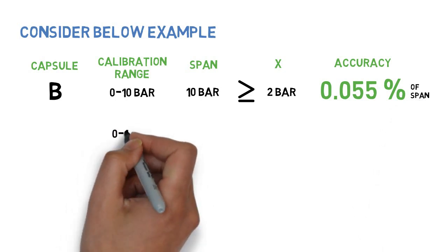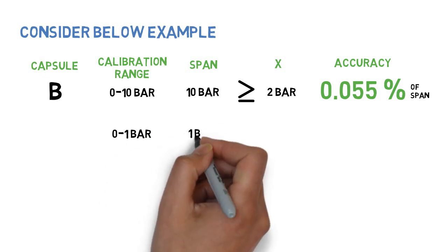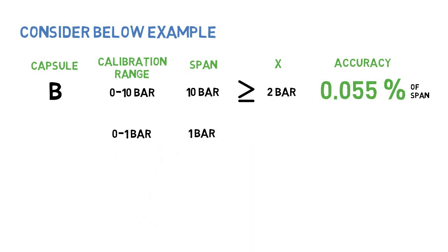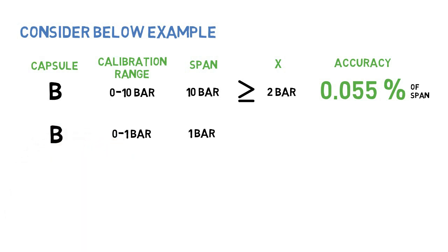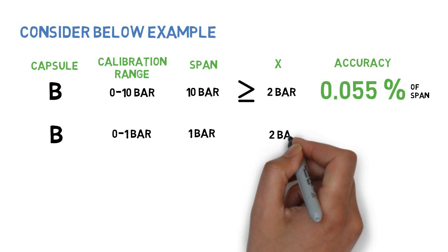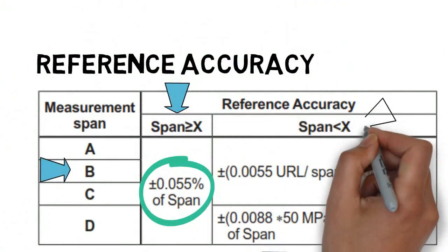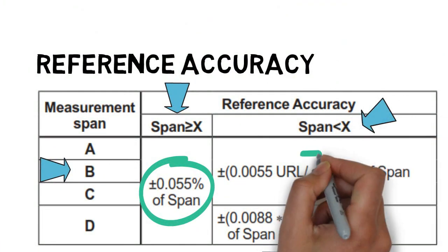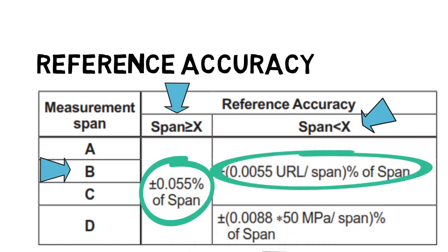Consider another range of 0 to 1 bar. Span is 1 bar. Maintain capsule same as B. Span is lesser than X. When span is lesser than X, accuracy shall be calculated as per formula given in this table.